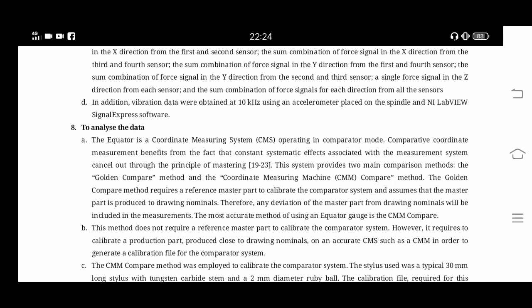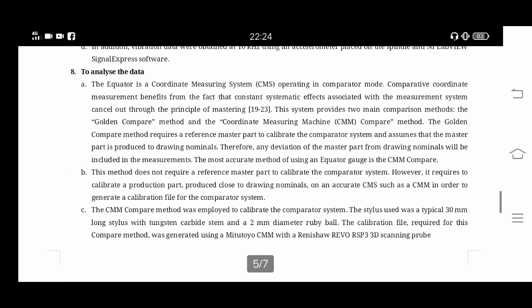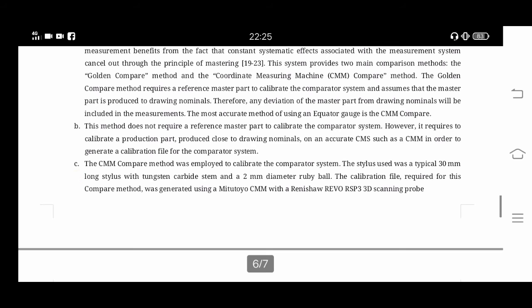The most accurate method of using an Equator gauge is the CMM compare. This method does not require a reference master part to calibrate the comparator system. However, it requires calibrating a production part produced close to drawing nominals on a coordinate measuring system such as a CMM in order to generate a calibration file for the comparator system. The CMM compare method was employed to calibrate the comparator system.